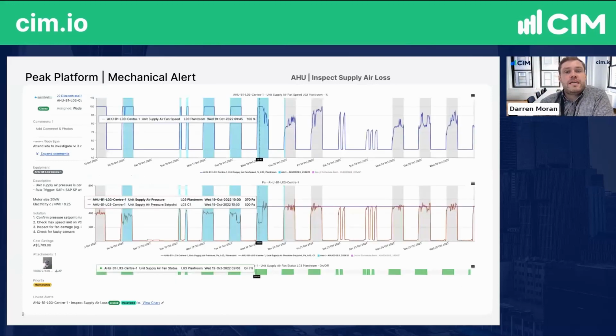As you can see from the chart, the AHU supply fan speed is operating at 100%. But if we look at the supply air set point, we are looking to achieve 500 PA, but we're only achieving 270 PA. So there's clearly an issue here somewhere.